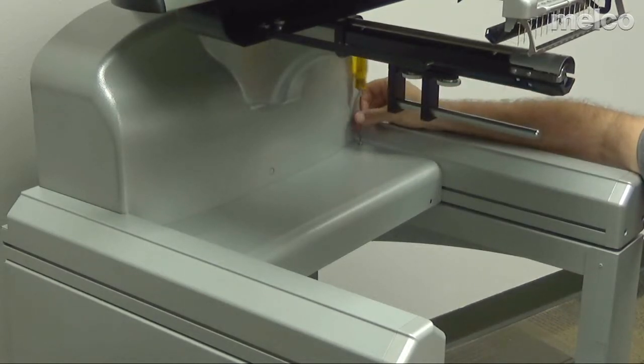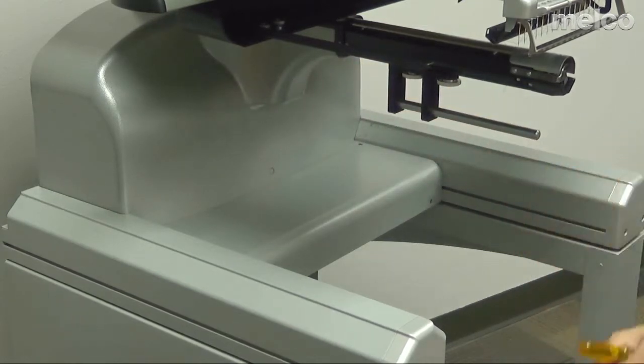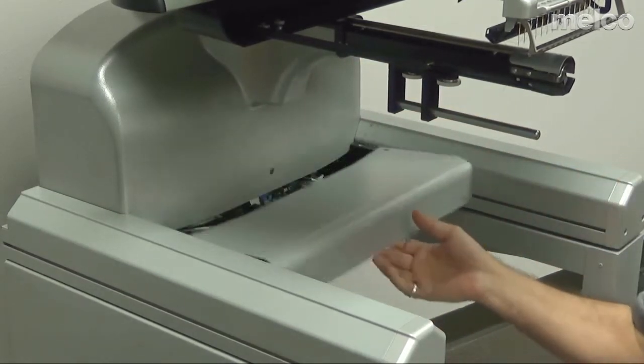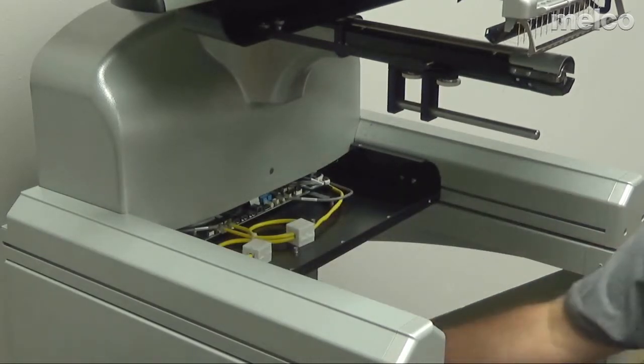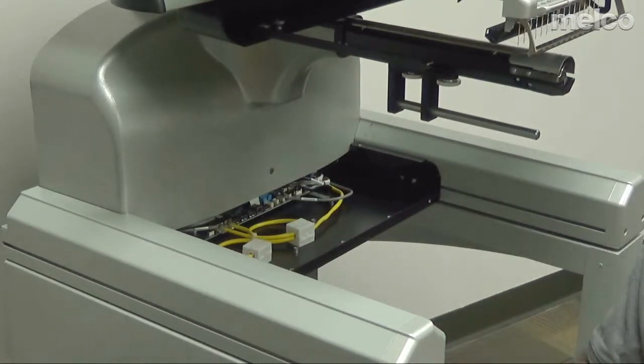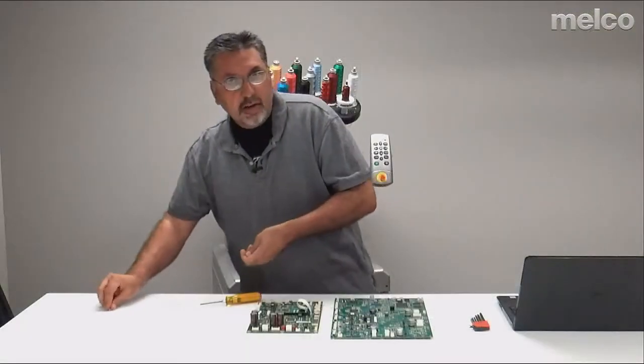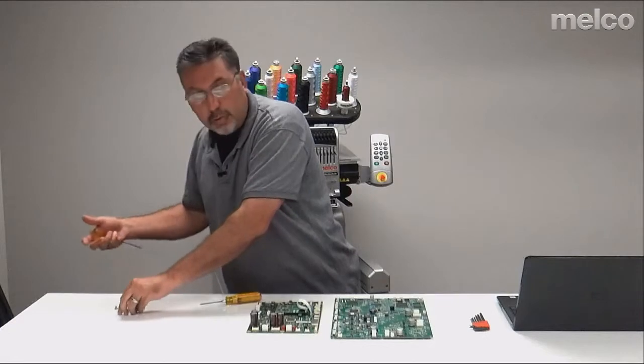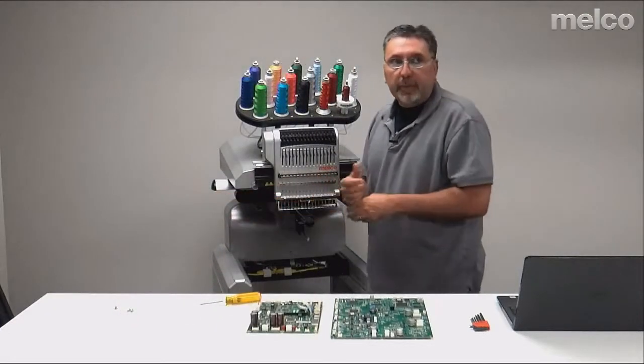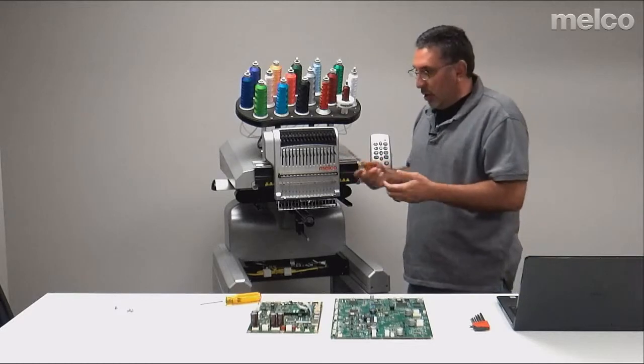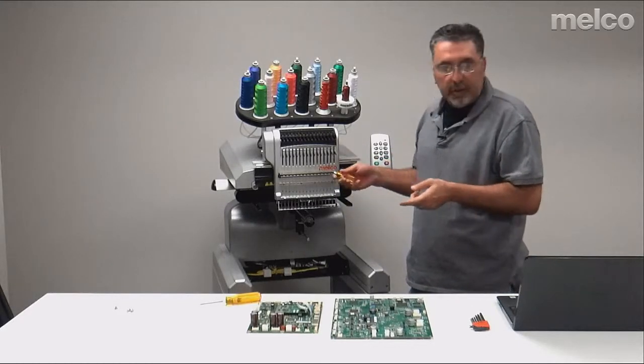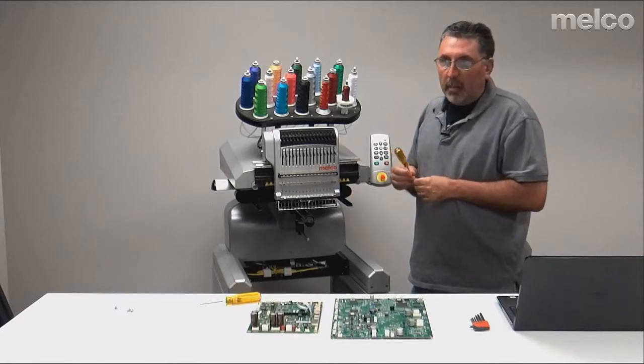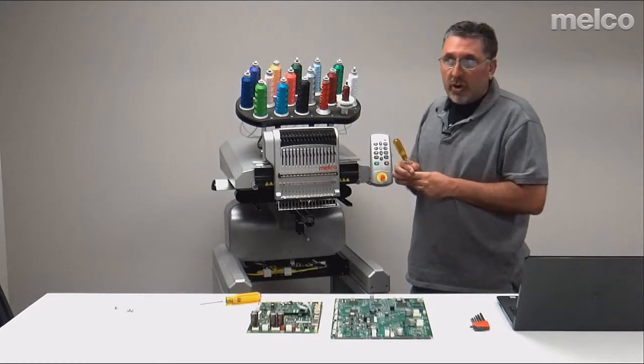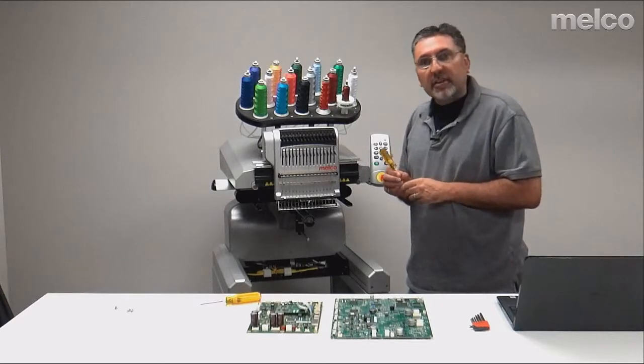Not being able to get the machine to communicate with the operating software would be one. Now again, let me preface that this is just some reasons. There could be other reasons for these causes that I'm listing that you would need to call tech support and troubleshoot first before you went to replace the main board. But loss of Ethernet communications, can't get the machine to talk to the software, XYZ tracking or timeout errors, things of that nature.